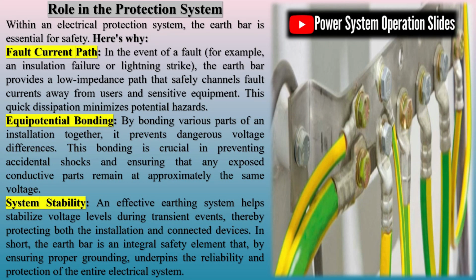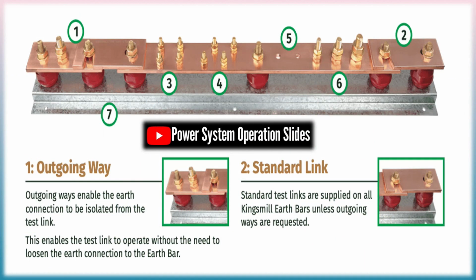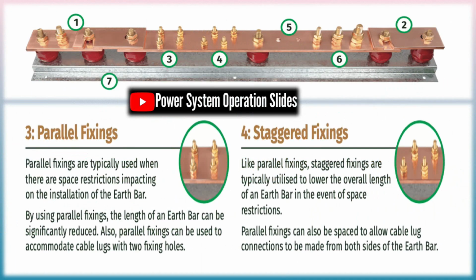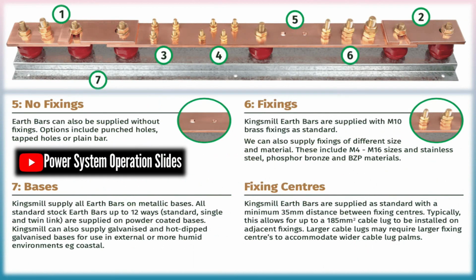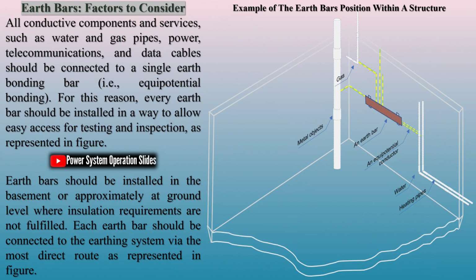Earth bar fundamentals. An earth bar, also known as a grounding or bonding bar, is a key electrical component found in both distribution boards and larger earthing systems. Fundamentally, it is a metal conductor, typically made from copper or copper-clad steel, designed to serve as a common termination point for the system's earth or bonding conductors. Its primary role is to ensure that all metallic parts and enclosures within an installation are at the same electrical potential, thereby reducing the risk of electric shock or equipment damage during fault conditions.